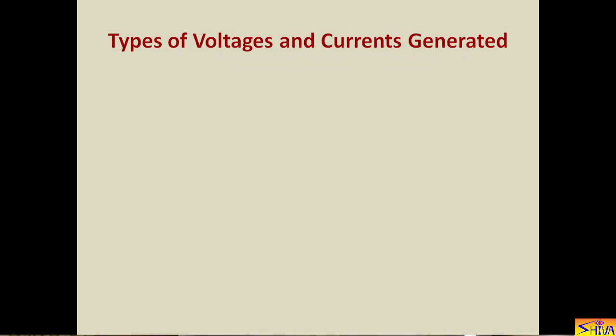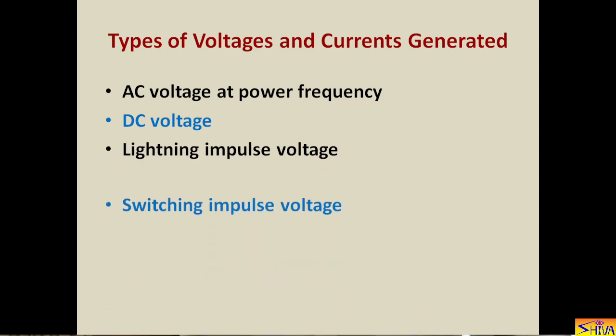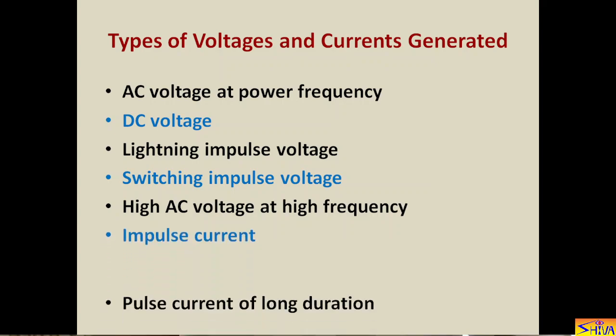Now let us see the types of high voltages and currents generated in the lab. Number one: AC voltage at power frequency. Number two: DC voltage, because nowadays at many places transmission is HVDC. Number three: lightning impulse voltage. Number four: switching impulse voltage. Number five: high AC voltage at high frequency. These are the five different types of voltages generated for testing. For current: impulse current as well as pulse current of long duration — these two types of currents are required to test electrical equipment.